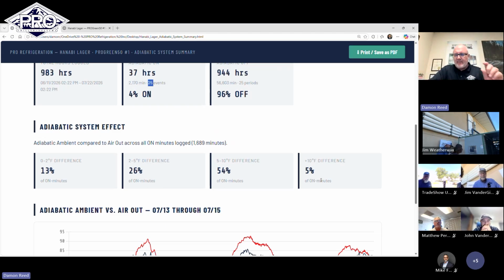I'm going to explain that a little bit from the adiabatic mindset. When we first turn on at 85, we're not going to see an immediate change of temperature. We need a little bit of time to wet that surface, or people will say charge the adiabatic surface. So we've got some charge time where we're not going to have a big delta. The temperature is going to change more once we get that adiabatic pad charged. Then, because we're coming on at 85, most of the time ambient temperatures are climbing. The hotter and the drier the air gets coming into that adiabatic pad, the bigger the range, or the wider the gap, we get on temperature difference. So we can see that.